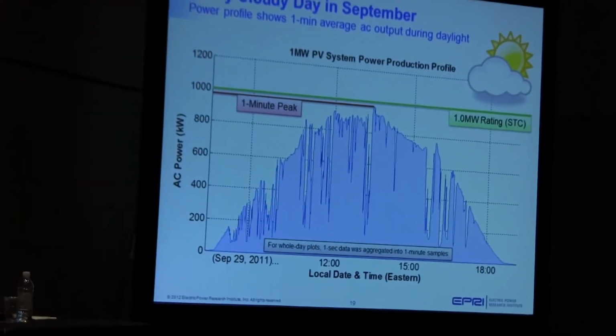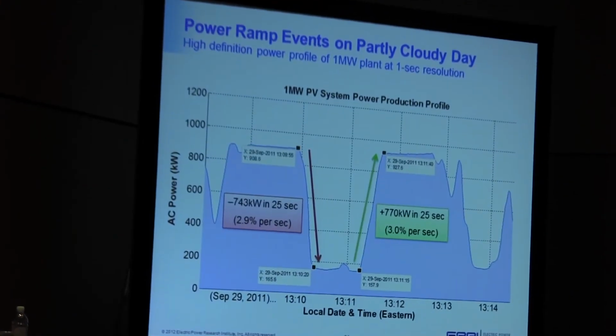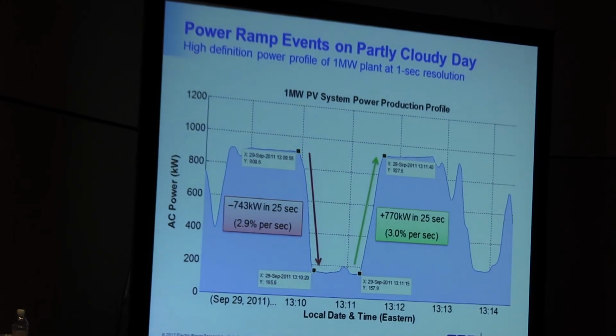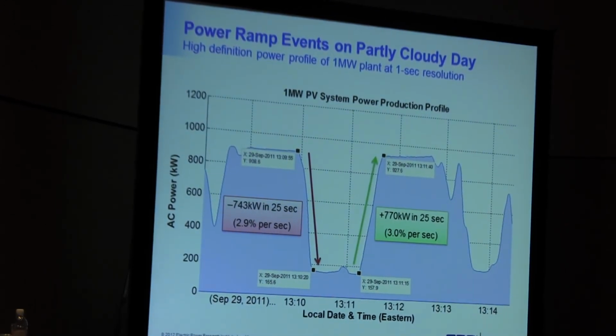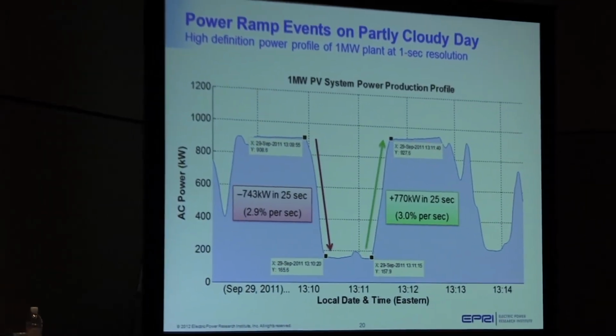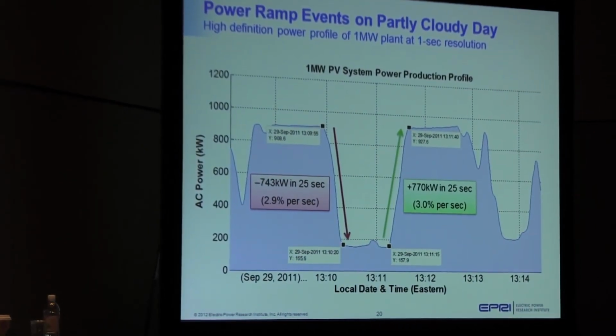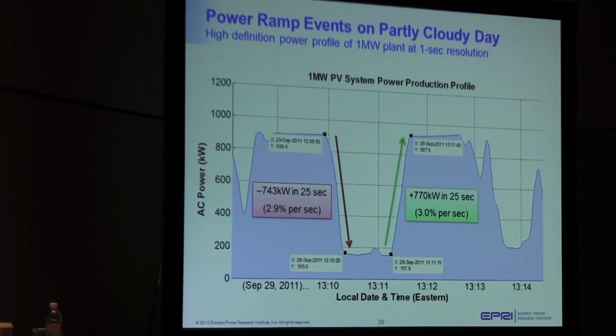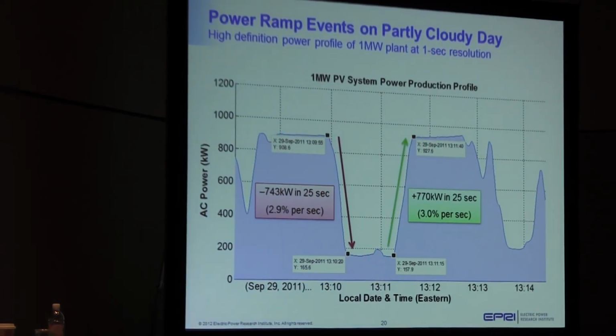In just a moment I'll show you some 1 second data. Here's a cloudy day on September 29th last year, looking at 1 minute average values, and you can see some good variability here. Zooming in on about the 1 o'clock hour in the afternoon, you can see about a 3% per second ramp down, then a minute later a 3% per second ramp up event. So we're able to sweep about 75% of this megawatt site in just half a minute.